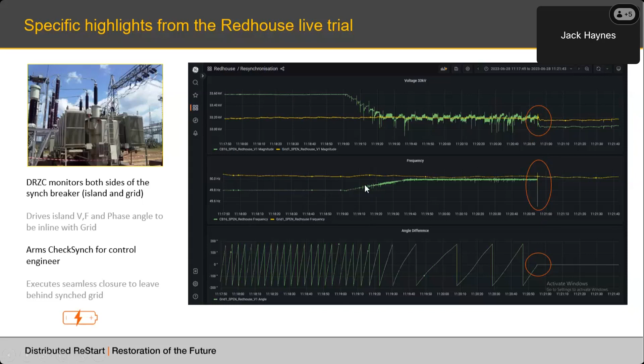We deliberately pushed the voltage and frequency of the island away from the grid, and then at about 11:19 or so here, you can see that the DRZC is armed to start tracking the voltage and frequency of the grid. So it's using the load bank and the BESS to push the voltage, frequency, and phase angle of the island to be closely in line with that of the grid. And then when it's within a particular threshold, in our case it was 5%, as highlighted by the orange element here, that's when the DRZC armed the circuit breaker for closure. You can see following the closure that the voltage, frequency, and phase angle are in line, so it left behind a kind of seamless closure following the checksync functionality.